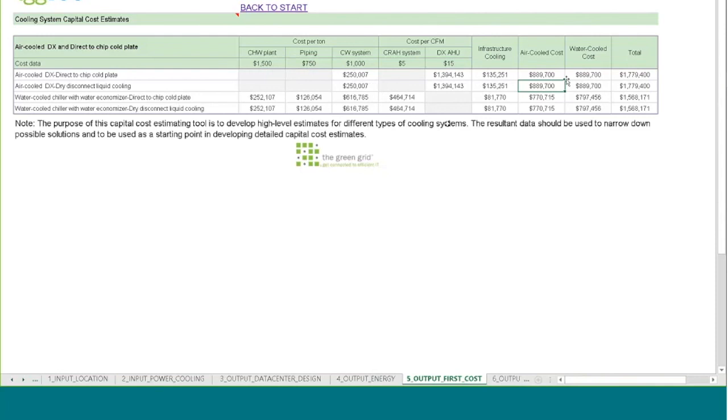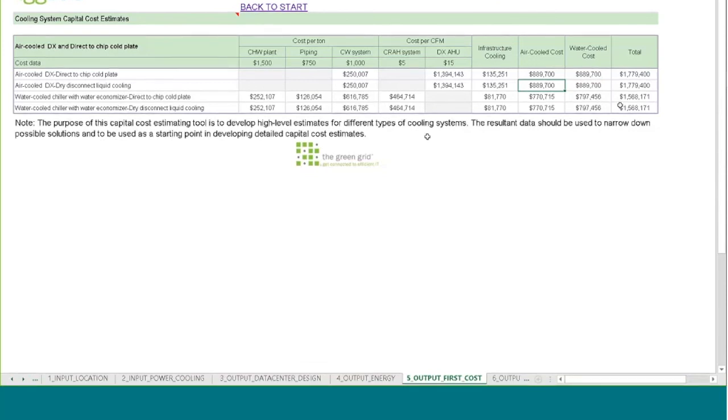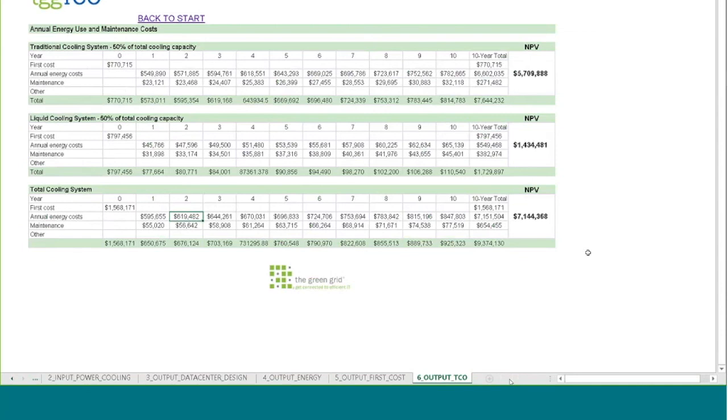So at the end here, we have air-cooled and water-cooled. These are just two systems that are in there right now. They're the same. So we find out that, in this case, the water-cooled is, whatever, $200,000 less in first cost. It's in this particular analysis. So in the future we may have this where the user could modify this to their own taste and keep the structure of the analysis intact, but we'll look at that when the time's right, after we start getting some comments.